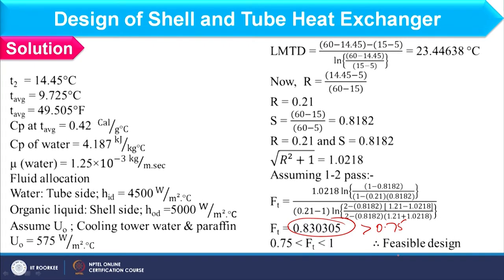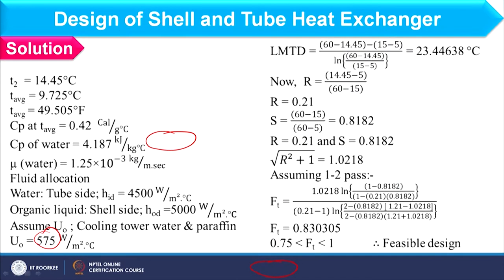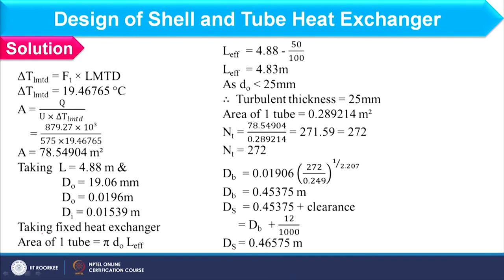Next, we find the assumed overall heat transfer coefficient U₀ from the graph. Considering the fluid combination, the assumed value of U₀ comes as 575 W/m²°C, as seen in the benzene-water case. With the LMTD value, the FT correction factor, and the overall heat transfer coefficient, we can now find the heat transfer area as 78.549 m². Tube length and diameter are chosen in the same manner as discussed in Lecture 15.